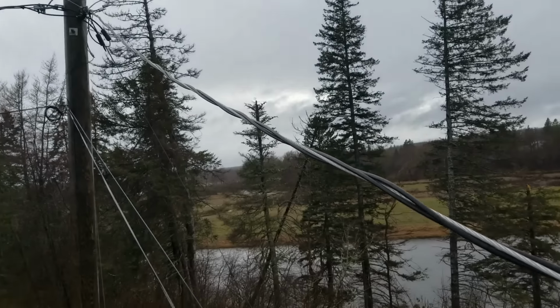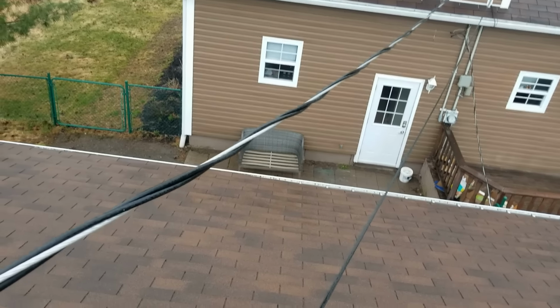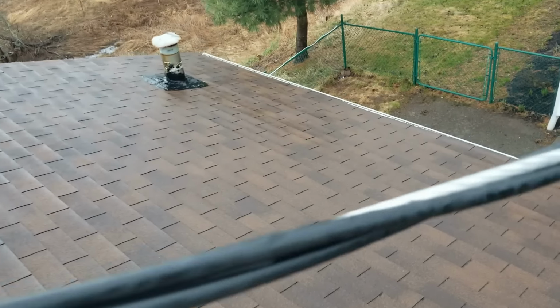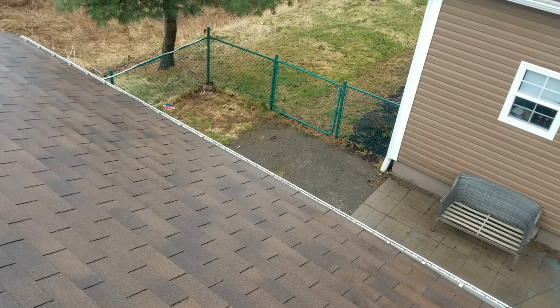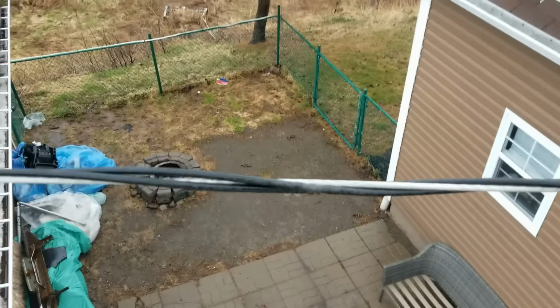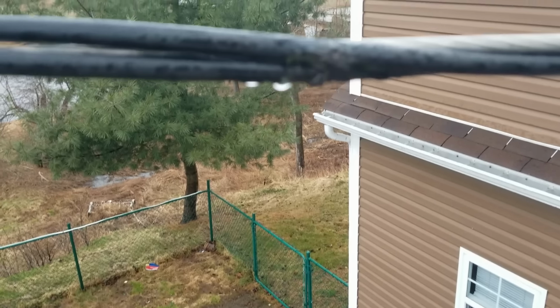I gotta say, this is a strange call. So we got our 240 volts there. We checked out the wire all the way to the house, at which point we lose all voltage. As you can see, this wire is in pretty good shape. I did find one little thing though. Right here. You can see there the wire looks a little funny.